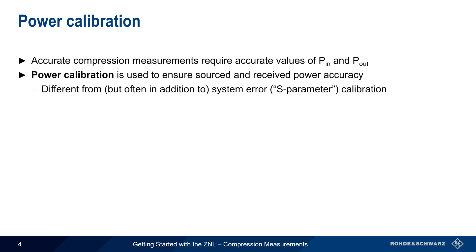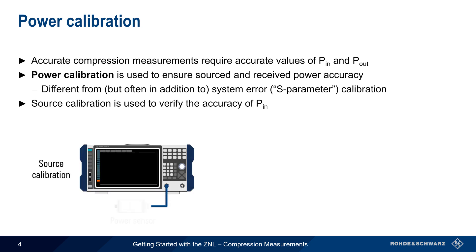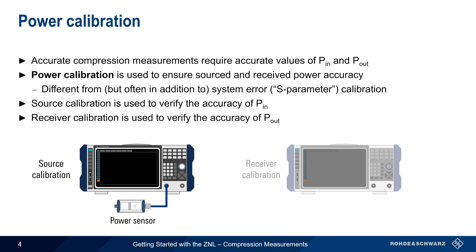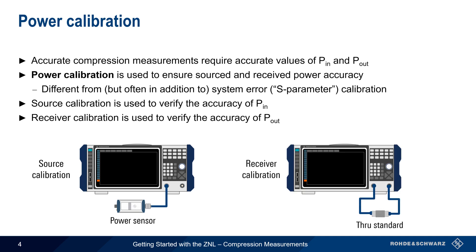There are two types of power calibration. The first is source calibration, which uses an external RF power sensor, or meter, to verify the accuracy of the source power. The second is receiver calibration, which is used to verify the accuracy of the measured power. We won't cover power calibration in this presentation, so please see the separate presentation on power calibration to learn more about this topic.